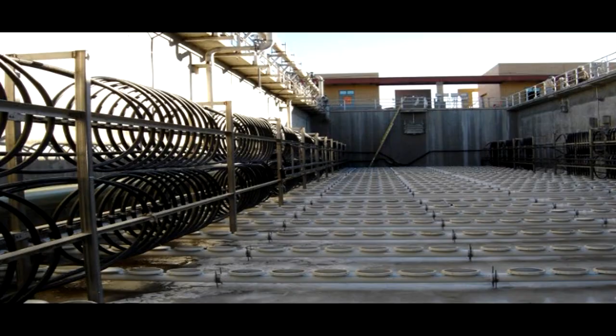I'm going to finish with probably one of our favorite jobs we designed and installed. This is the City of North Glen Wastewater Treatment Facility, the wash basin slinky loop. They came to us and said, guys, these wash basins are going to be full up to the top with water that's basically 50 degrees year-round—they're aeration basins, cleaning the sludge. So rather than drill or dig, we built a series of stainless steel racks and hung our coils in each one. There are actually 3 of them, because one's always down for cleaning while 2 run, so there are always 2 heat exchangers available to heat and cool the building and the facility. That's how it ended up working out.